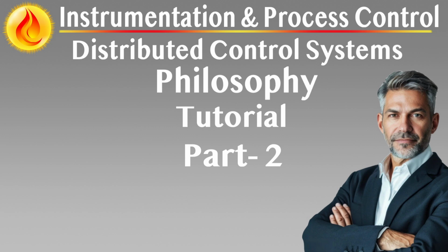Synchronized interlocks and action propagation. The ESD system maintains real-time connectivity with the fire and gas system (FGS), rotating equipment protection systems, and other safety-critical subsystems. Shutdown triggers from these systems are propagated across all relevant equipment in a coordinated, cascading logic using digital interlocks and SIL-rated safety relays or secure protocols.